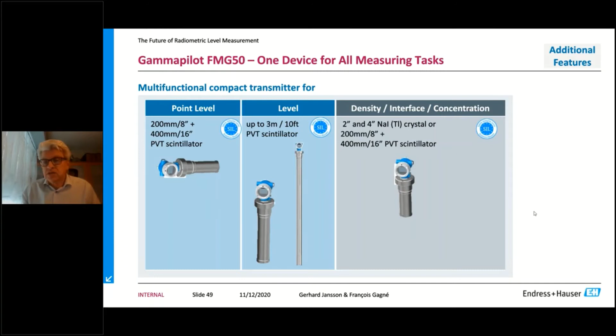Density. There we have the two options of detectors, either the sodium iodide crystal or the PVT detector. They are different lengths, and this has very much to do with what the line size and the density range are. Usually when you have line sizes up to somewhere around 8 to 10 inches, then you typically do the 2 or the 4 inch sodium iodide crystal. It will give you a very good accuracy. If you have larger line sizes, then we can use the PVT detector. Yes, it doesn't have that stability, but it will still give you a very good accuracy if you have a larger line size. And you'll see later on that we will have some of both of those detectors.